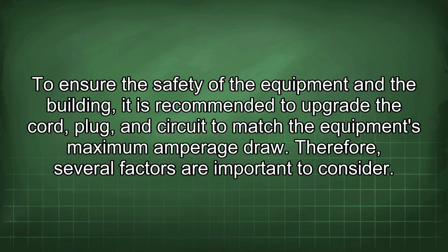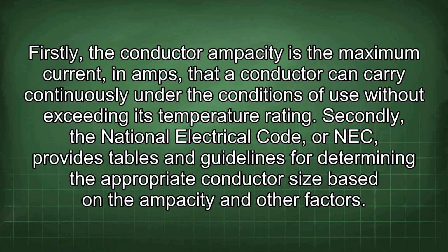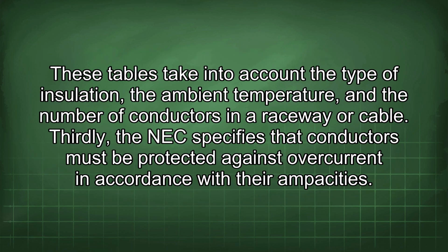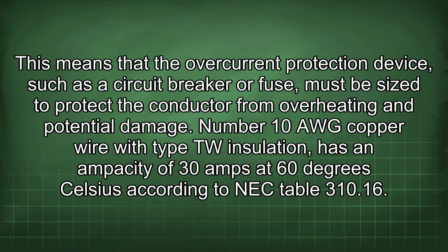Therefore, several factors are important to consider. Firstly, the conductor ampacity is the maximum current in amps that a conductor can carry continuously under the conditions of use without exceeding its temperature rating. Secondly, the National Electrical Code, or NEC, provides tables and guidelines for determining the appropriate conductor size based on the ampacity and other factors. These tables take into account the type of insulation, the ambient temperature, and the number of conductors in a raceway or cable. Thirdly, the NEC specifies that conductors must be protected against overcurrent in accordance with their ampacities. This means that the overcurrent protection device, such as a circuit breaker or fuse, must be sized to protect the conductor from overheating and potential damage.